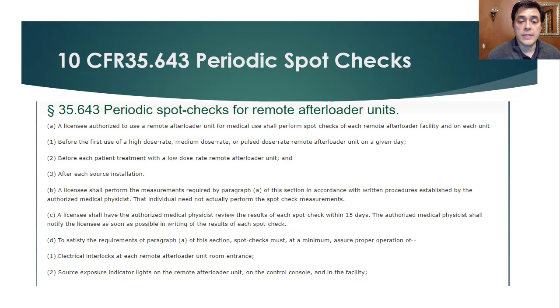So the authorized medical physicist should review the results of the spot check, and for this spot check, at minimum, you must assure the proper operation of the electrical interlocks. So for each of the afterloader's entrances, there is a way to disable the source if the door is opened. The interlock needs to be checked. The source exposure indicator light on the afterloader unit, on the control console, and in the facility or in the hallway that's adjacent to that room needs to be checked.